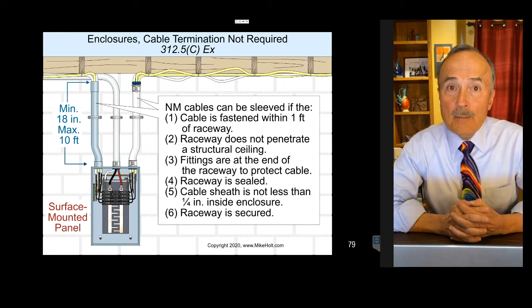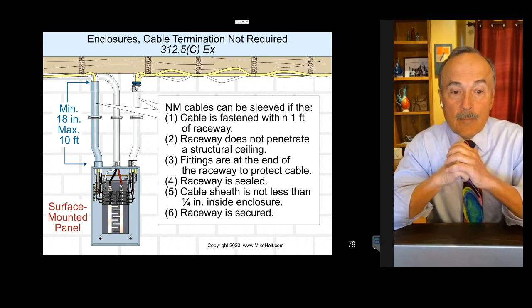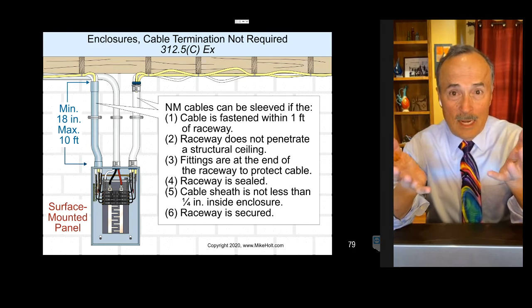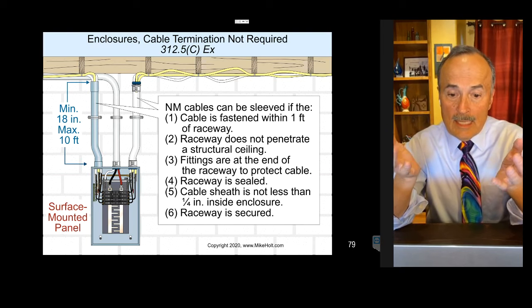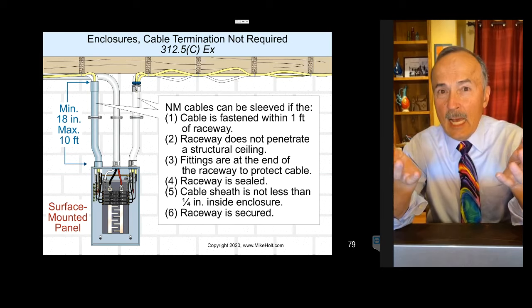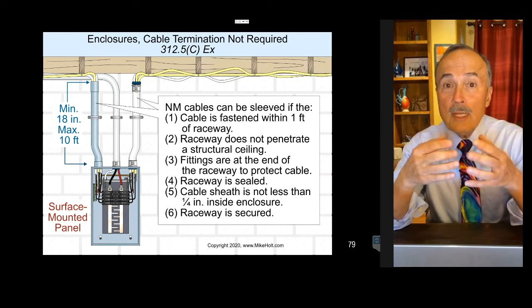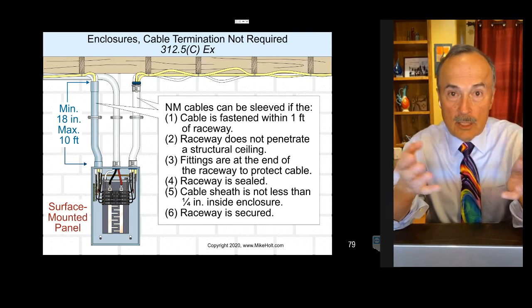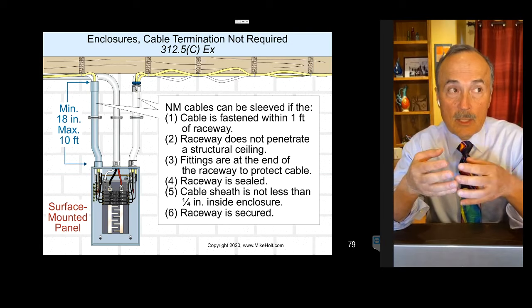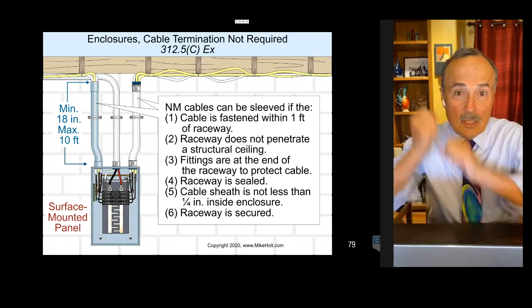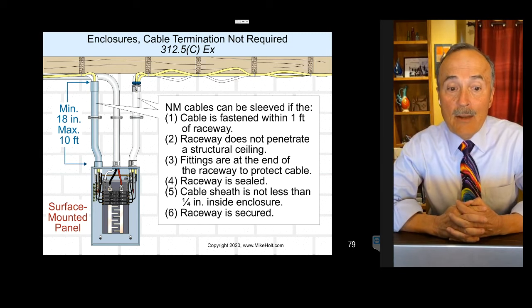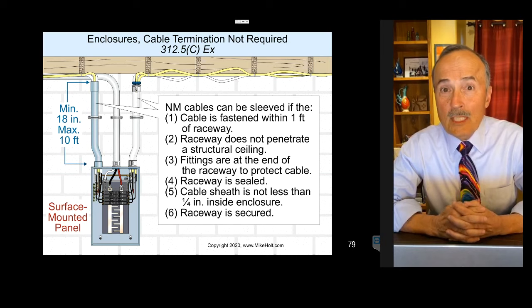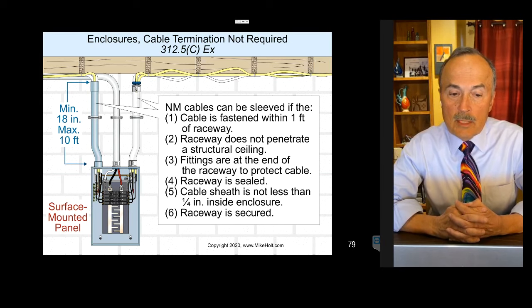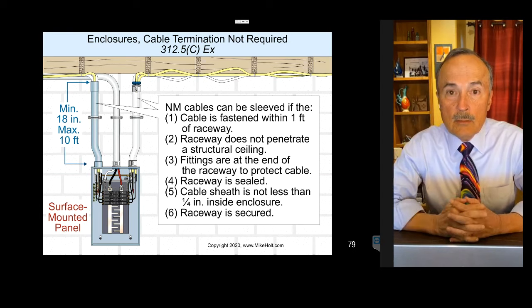So I'm going to ask Mike Corbett, my graphic designer, who's watching this, let's change that to, wow, what could you use? I guess you'd have to put a PVC coupling. No, I'm sorry, a PVC connector on there, because there's nothing in the code that tells us exactly what kind of fitting to put on the end there. Fittings are at the end of the raceway to protect the cable. So that's going to be a 90.4, the authority having jurisdiction. You're putting in cables. It isn't like you're putting in conductors. You know what I mean? There's a difference in pulling conductors in a raceway than there is putting in cables. And basically you're not really pulling them, you're just kind of pushing them down, because you can see there's a maximum length of. So I don't know what the authority having jurisdiction would say.